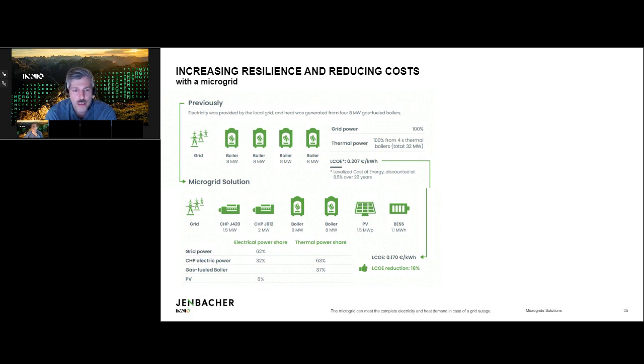We still have two of the original gas-fueled boilers installed as backup in case of low electricity but high heat demand. We also have battery storage systems used for peak shaving, reducing demand charges, and all the benefits shown before, including enabling energy arbitrage with approximately one to two charge and discharge cycles a day.